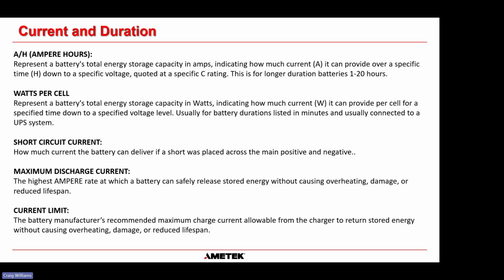The next terminology is current and duration. The most popular one is ampere hours, designated AH. It represents a battery's total energy storage capacity in amps, indicating how much current it can provide over a specific time down to a specific voltage, quoted at a specified C rating. It's usually used for longer duration batteries, anything from 30 minutes up to 20 hours.